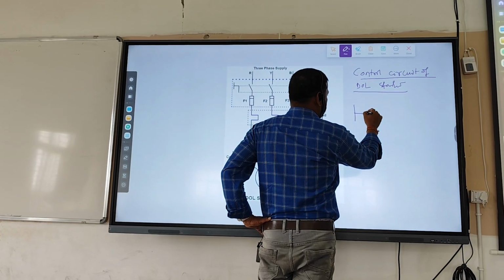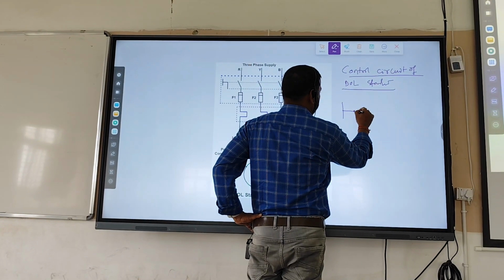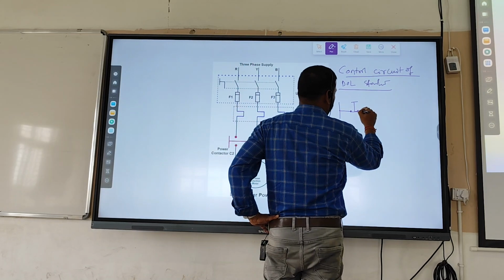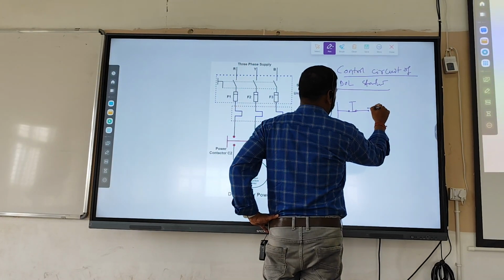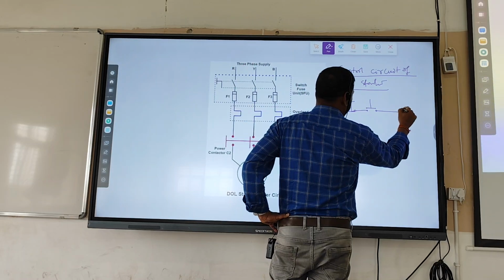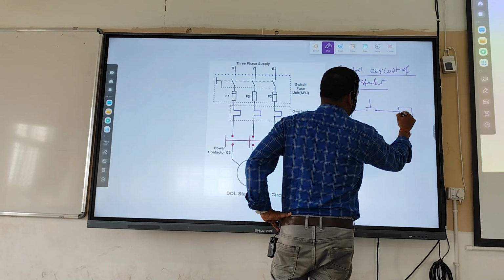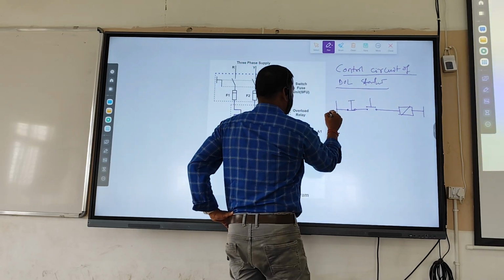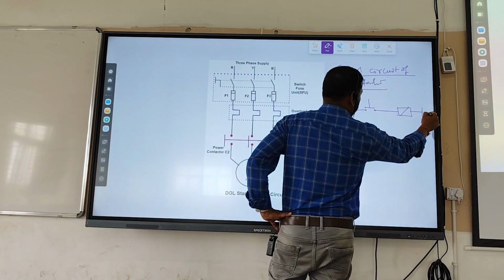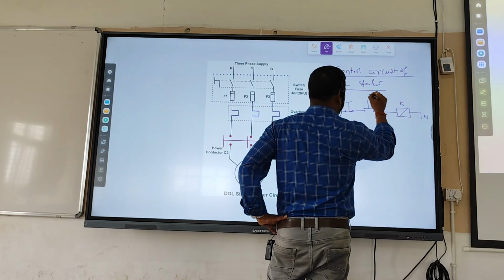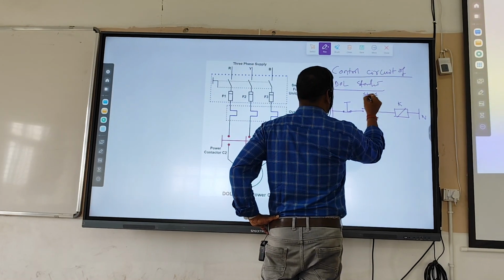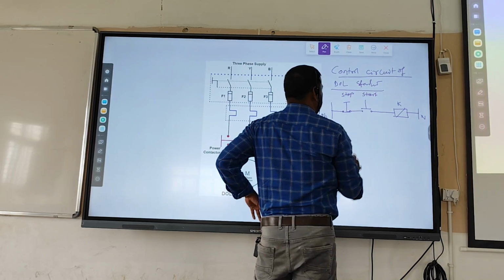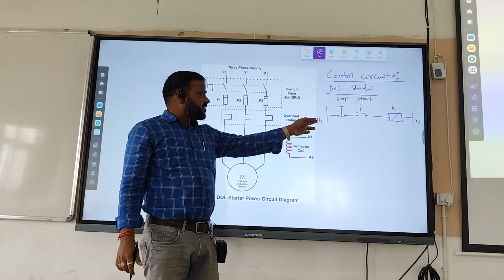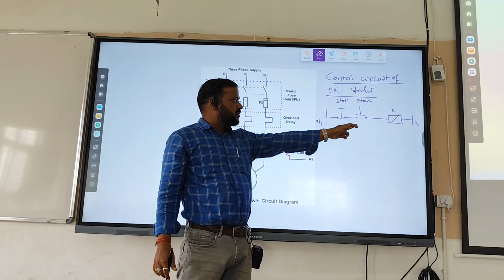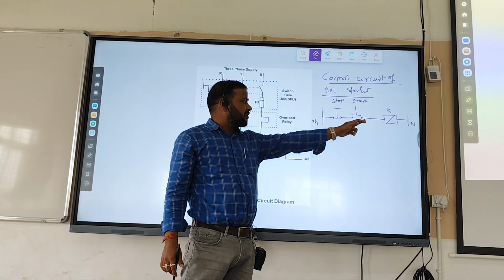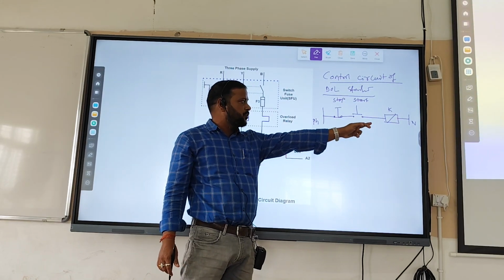Let's say this is your stop push button. Then the start push button. Then this is the contactor. Let's say this one is phase, and this is neutral. So from this you can understand: phase, then stop push button, start push button, then contactor. One end of the contactor coil is connected through the start push button and the other is connected with the neutral directly.